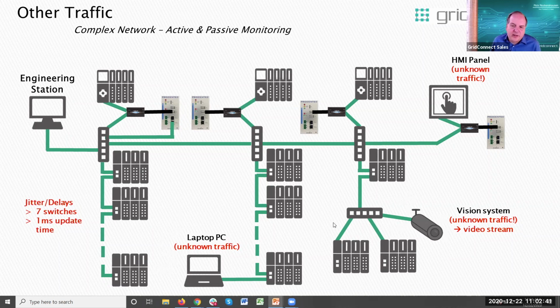Without Atlas, you wouldn't know that this vision system is really congesting the links between it and the engineering workstation. Without it, you wouldn't know if your jitter or delays are becoming a problem—if you go through more than 7 switches between controller and device, that can affect your update time. There's lots of stuff going on. HMI panels don't always talk just the protocol of the network they're attached to; they often generate a lot of other unknown traffic. So the impacts of those are really unknown unless you have an Atlas checking it out for you.